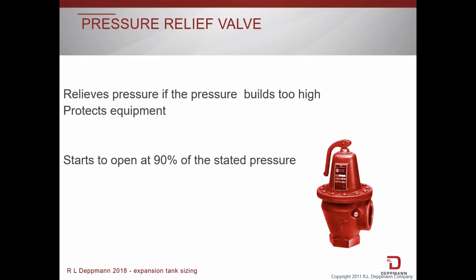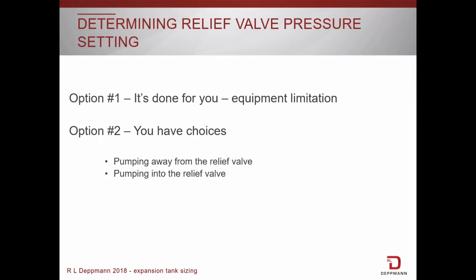Now the question is, what pressure setting do we need? The setting is determined one of two ways. First, it's given to you. The relief valve on some boilers have one or two options. You might see this on smaller residential type boilers that are traditionally set at 30 psi. The second is your given choices.